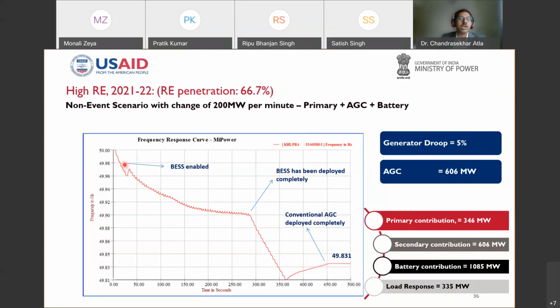So this is the study we have done. BESS started deploying instantly within the 5 seconds to 10 seconds range. The frequency changes every minute continuously, with steps of 200 megawatt per minute. So the frequency starts falling by this 250 megawatt, and all your BESS has been deployed. Further, we also have the secondary reserves, which come from various sources. Please note that all the secondary reserves will not deploy at the instant they are enabled, because depending upon the generators' ramping and their response time, they deploy slowly. Finally, after deploying the complete primary BESS and the secondary, the frequency settles at 49.8, which is above our limit of 49.5.